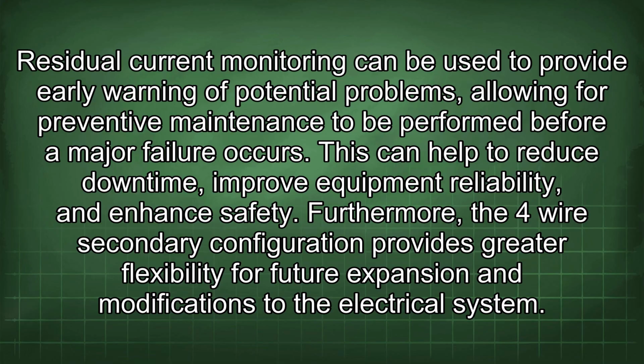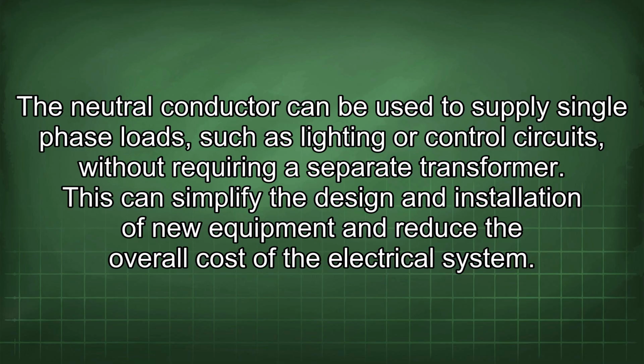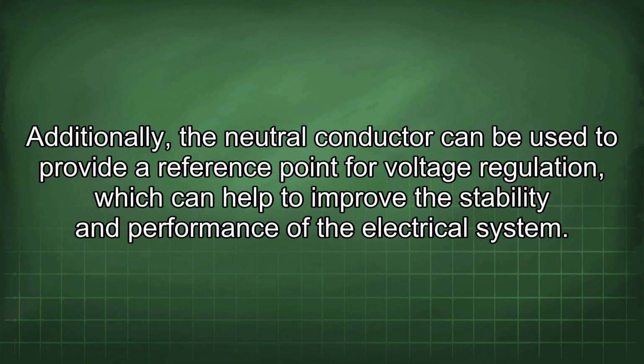Furthermore, the 4-wire secondary configuration provides greater flexibility for future expansion and modifications to the electrical system. The neutral conductor can be used to supply single-phase loads, such as lighting or control circuits, without requiring a separate transformer. This can simplify the design and installation of new equipment and reduce the overall cost of the electrical system. Additionally, the neutral conductor can be used to provide a reference point for voltage regulation, which can help to improve the stability and performance of the electrical system.